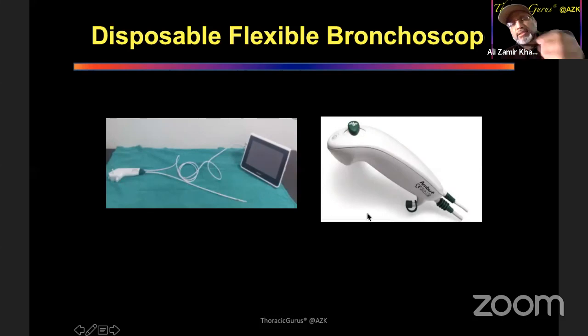So Ambu's are licensed for single use, but in India, I know that people use them for about 10 times. Not licensed, it's an off-license use. The other advantage of a disposable bronchoscope is that a normal bronchoscope has got fiber optic fibers running down the bronchoscope. So when you bend it too much, the fiber snaps. And when a fiber snaps, you get black spots. So over a period of time, when more inexperienced people are using a flexible bronchoscope, they will end up losing vision with each fiber, because each fiber is a pixel on the screen. So when the fiber disconnects or snaps, then you lose the picture.